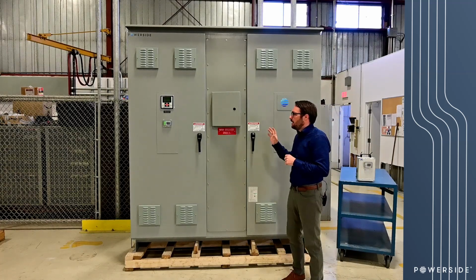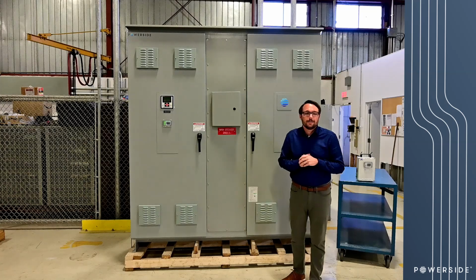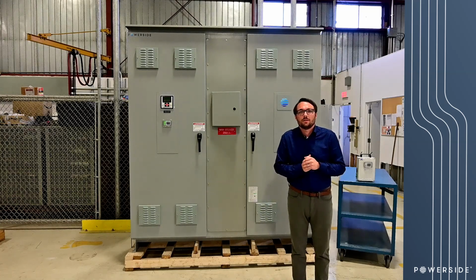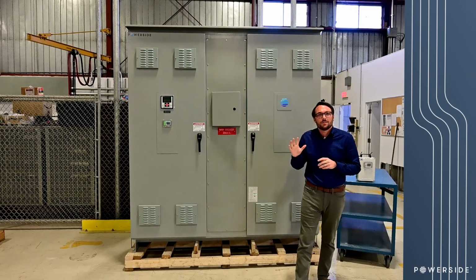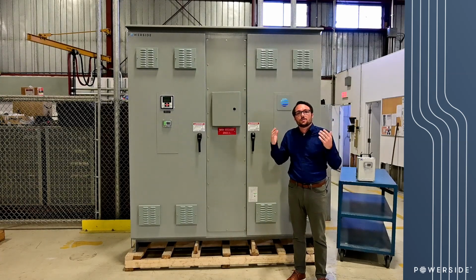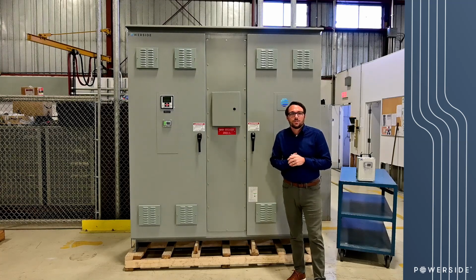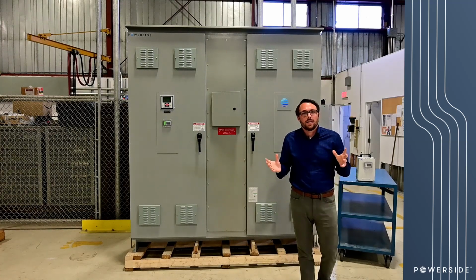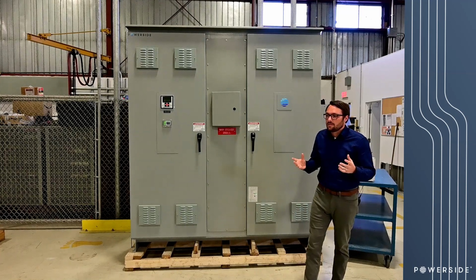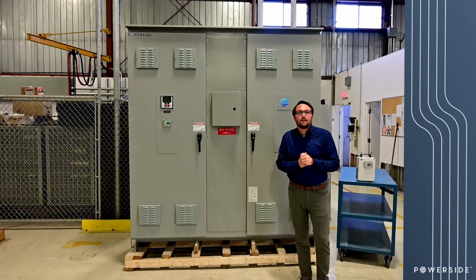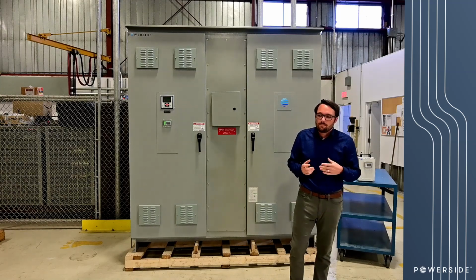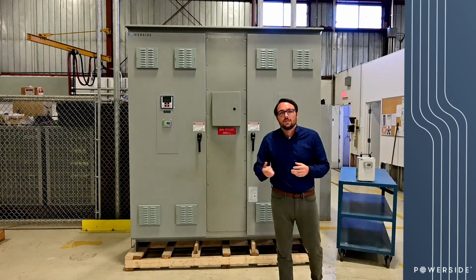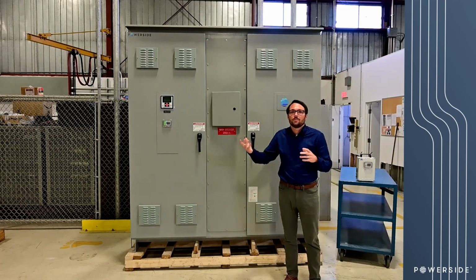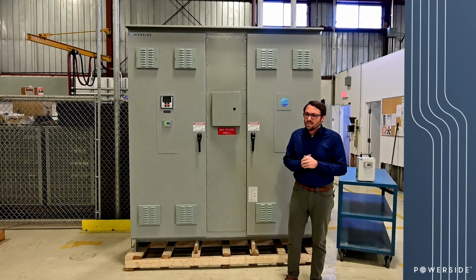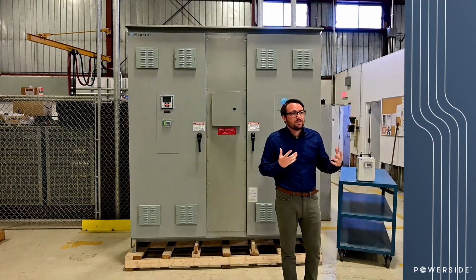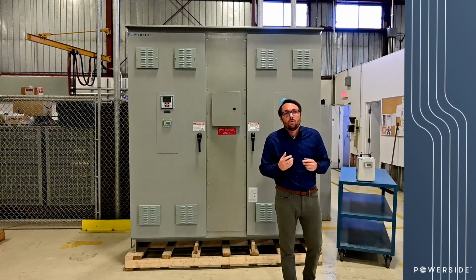So this client that ordered this product does aluminum extrusion. That's their operation. They have 5 services that are coupled to a 13.8 kV distribution line. Each of these services operates a press, and the operation of the press is fairly simple in nature. It takes a large billet of aluminum, presses it through a die, and extrudes it into a certain size, shape, dimension, length, etc. And that operation happens quite frequently throughout the day, over and over again.